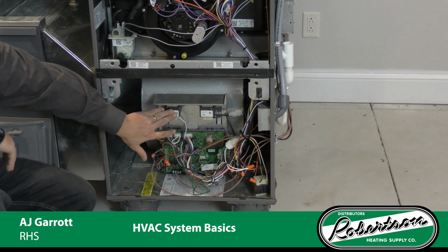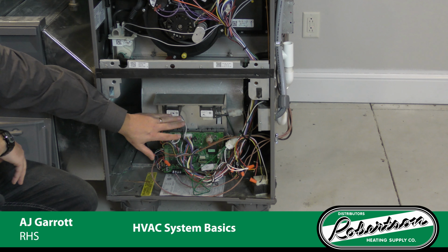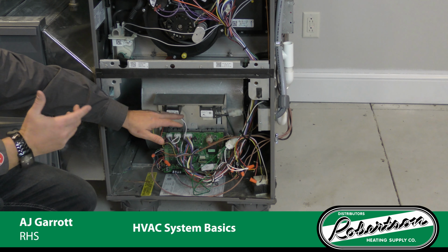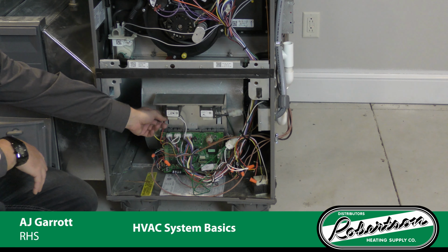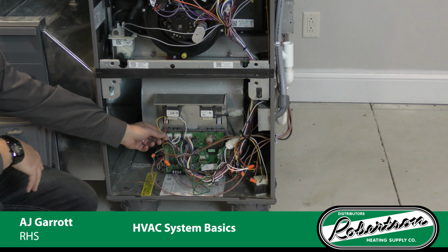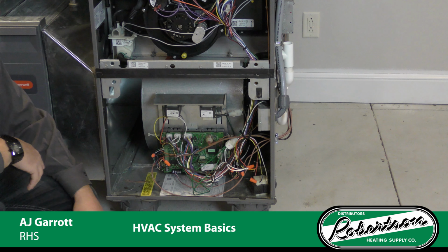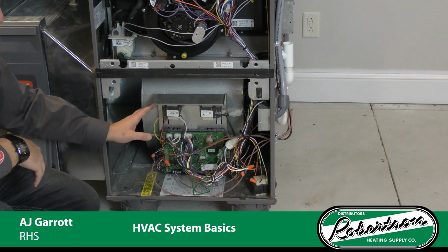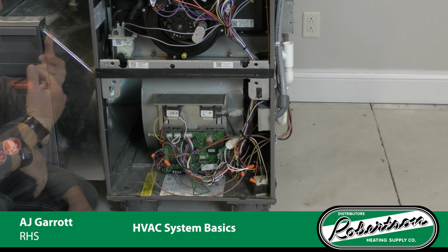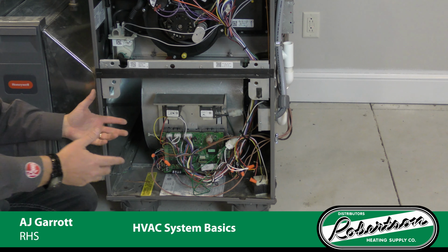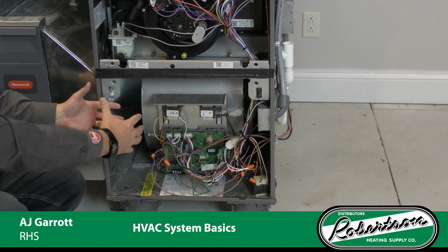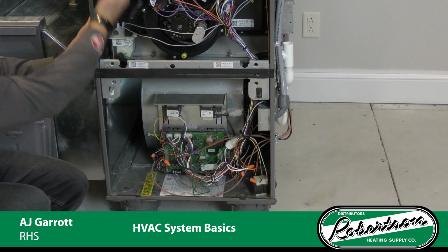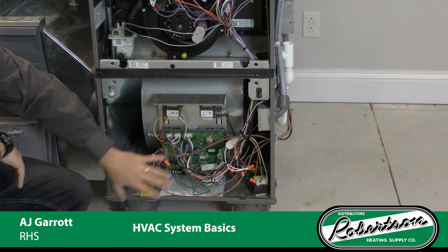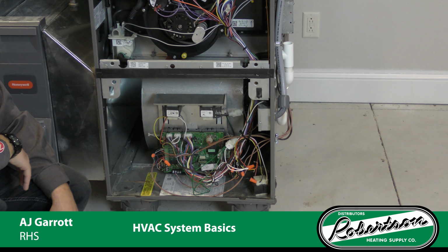We also have a transformer here. It takes 110 volts or 230 volts depending on your application, and takes that voltage down to a safe low voltage for all our control stuff. The blower motor and assembly section in here, it rotates a wheel inside there, which then sucks air from the return and pushes it up across the heat exchanger and out. That's all done down here in this application.